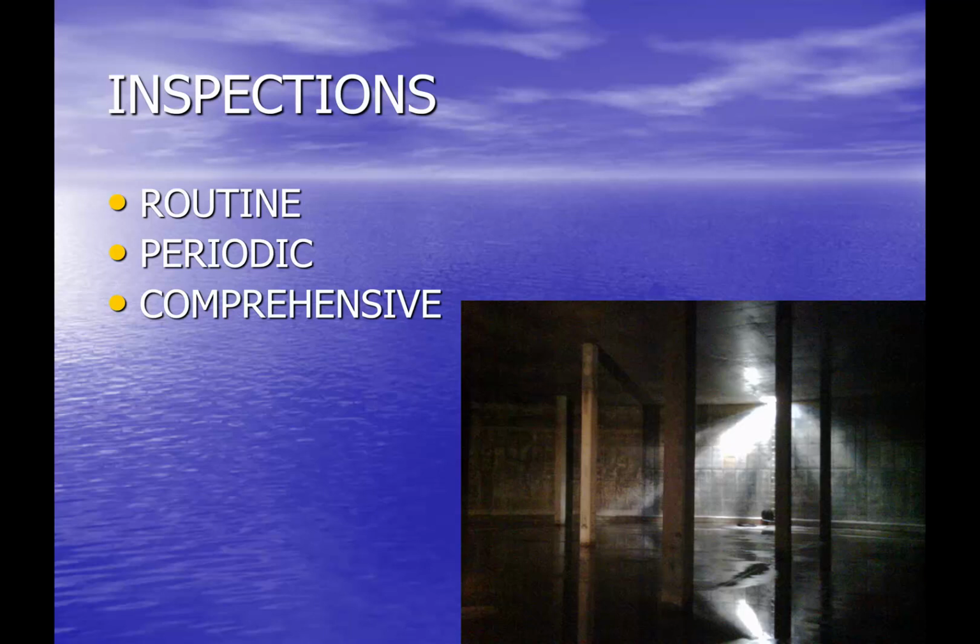I'm here to tell you we do not do a well, I take that back. We do do an inspection of the interior of our reservoirs every 2 years, but we do it with divers as opposed to draining the tank and going into it. But we're looking at things, we're looking for things in these kinds of inspections. Again, it's a much more detailed evaluation, especially of the interior.